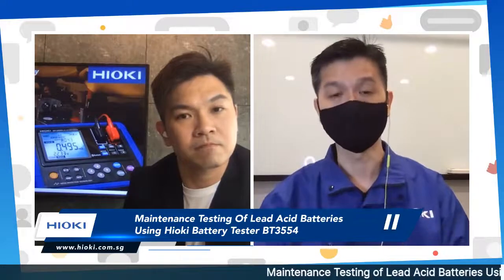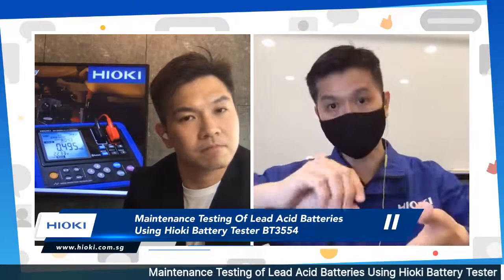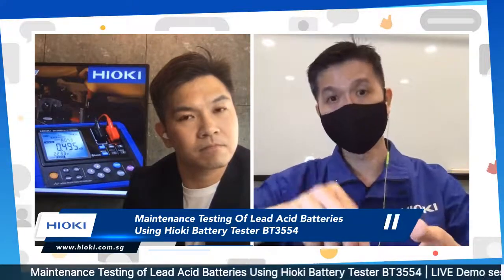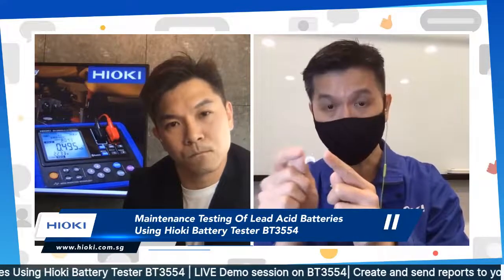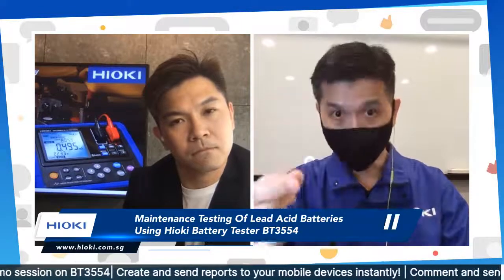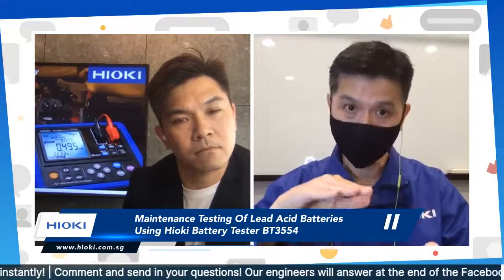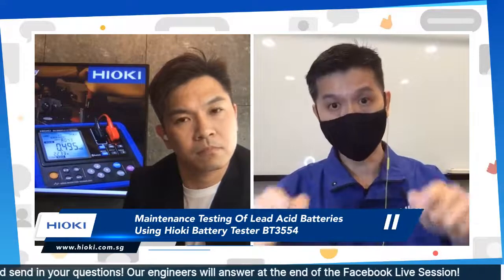So you open up the battery tester from the back, remove the blown fuse, or do a continuity check on the fuse first to make sure it's blown. If it's found to be blown, take the new fuse already provided inside the battery tester, insert it into the fuse compartment, turn it back on, and test again. If the resistance value and the voltage both appear, everything is fine and you don't have to send it for repair. That is the first diagnosis.